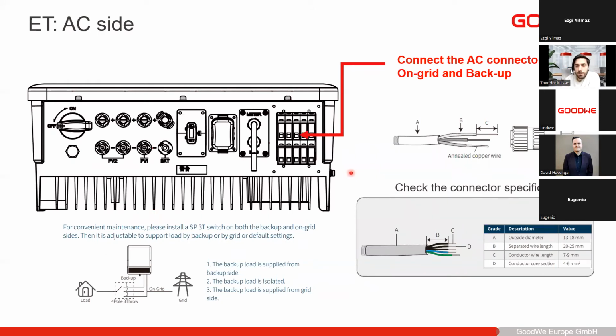So now everything is ready for the AC side, and then you just connect the AC cables here. Let's say you don't have the battery, but you already want to set up the possibility for the backup output for the future. Then I recommend that you already do the wiring, but with one of these switches, so that at a later stage you can put over all the backups to the backup output. For now, you can connect all the backups to this one. In this way, you can already do all the wiring on site, and at the later stage, when you connect the battery, you just need to turn the switch to put over all the loads on the backup switch.